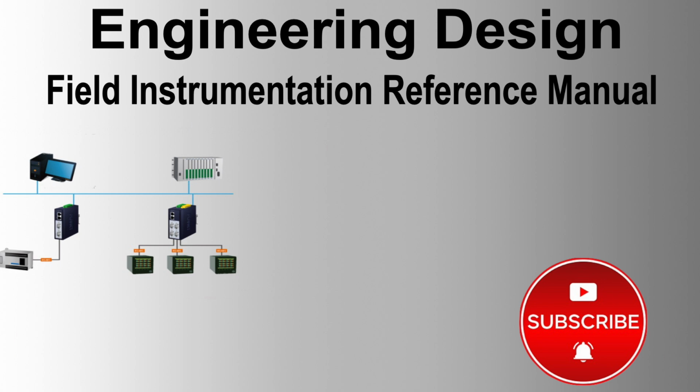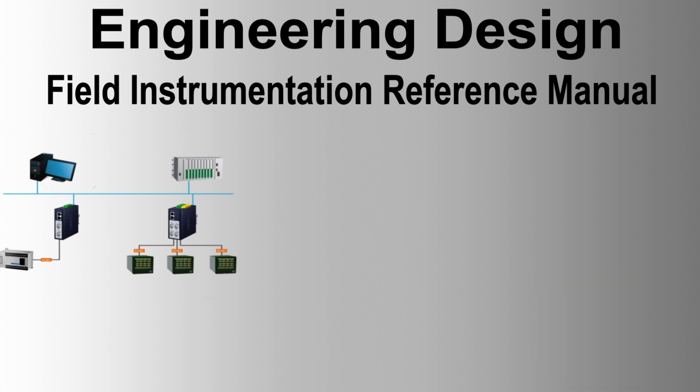2. Determine operating window. Gather all relevant process data for each operating case, including fluid data, fluid name, phase, physical properties, special aspects like corrosiveness, toxicity, etc., and operating data, flow rate, pressure, temperature, density, and viscosity. Consider application aspects such as continuous or batch operation, pulsating flow, unidirectional or bidirectional flow, backflow risk, mechanical integrity, vibration, and hydraulic noise.